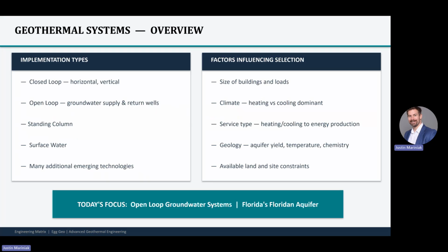To begin, we will mention there are several types of geothermal systems. They include closed loop, which is composed of a closed loop piping system of water run in the ground. The piping can be both horizontal or vertical. Open loop, which will be the focus of today's presentation, these systems transfer heat to and from water that is pumped out of the ground. There are also standing column, which are deep wells that contain a large column of water, as well as surface water exchangers, which transfer heat into and out of bodies of water. There are also other types of technologies that specialize using different compounds, such as CO2.